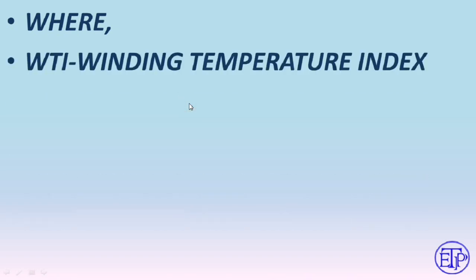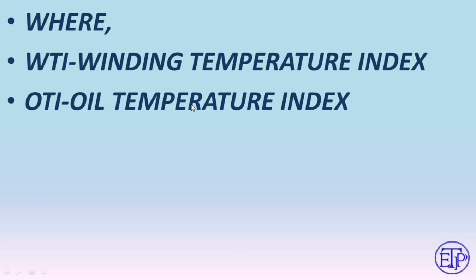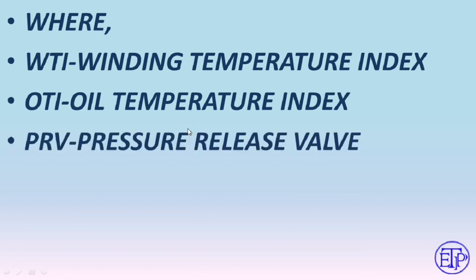WTI stands for Winding Temperature Index — it measures the winding temperature and raises an alarm at a set point, then initiates a trip if the temperature continues to rise. OTI stands for Oil Temperature Index, and PRV stands for Pressure Relief Valve.